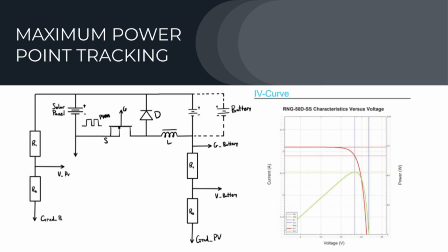Another notable characteristic is that when using solar panels, you need to adjust the power output so it is optimized for your battery conditions. If we were to connect the panel directly to the battery, we would reduce our efficiency by approximately 35%, since the battery and panel are spec'd at different voltages.